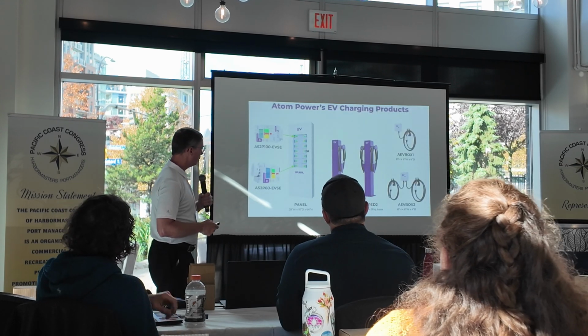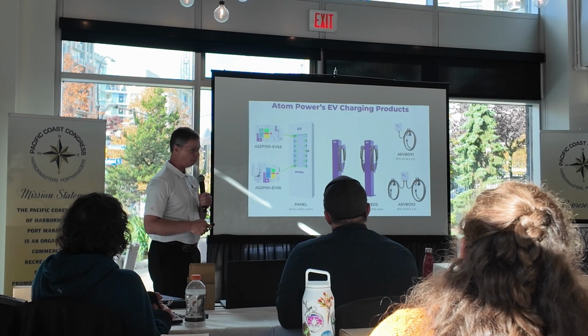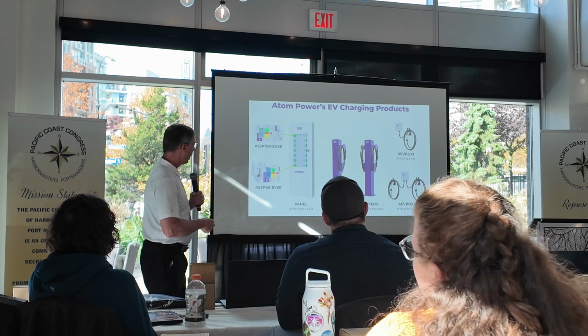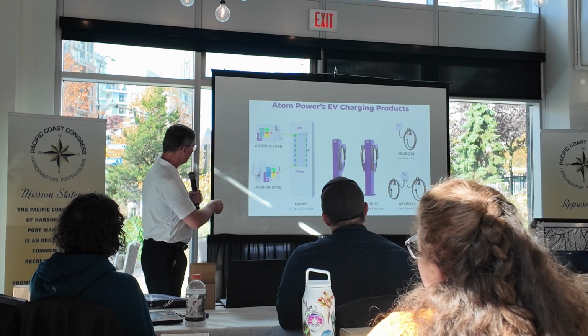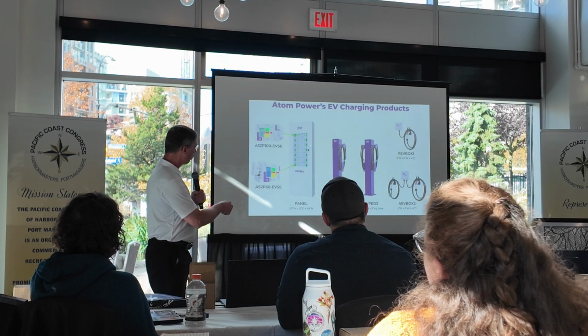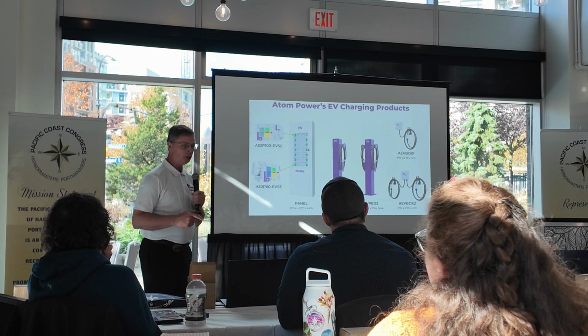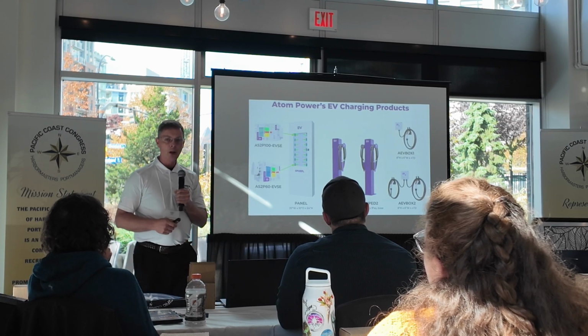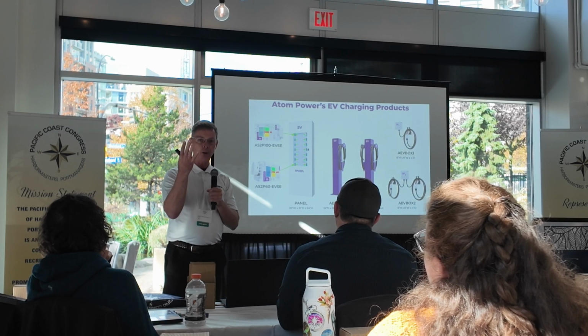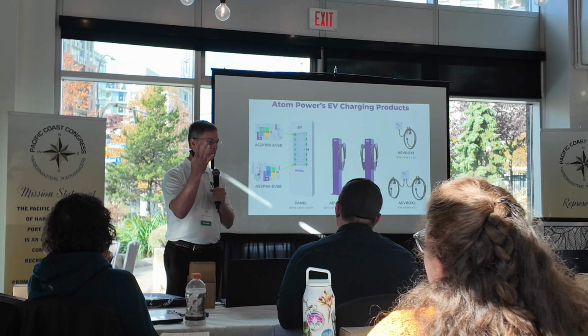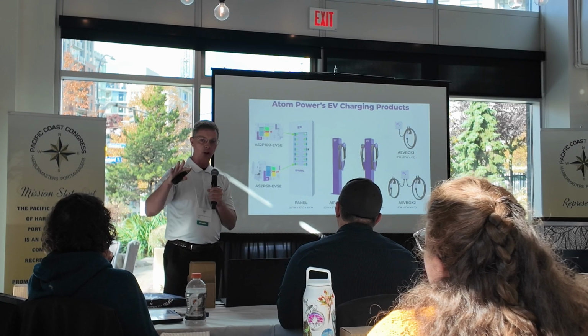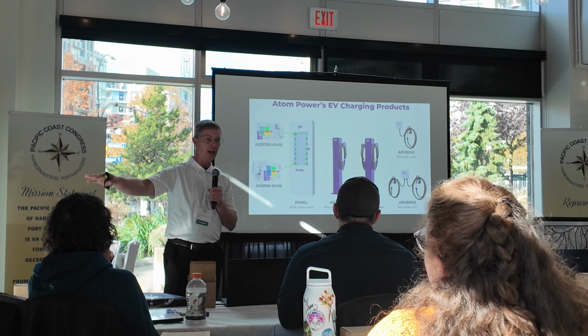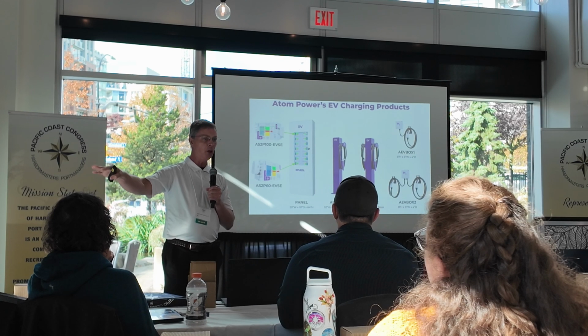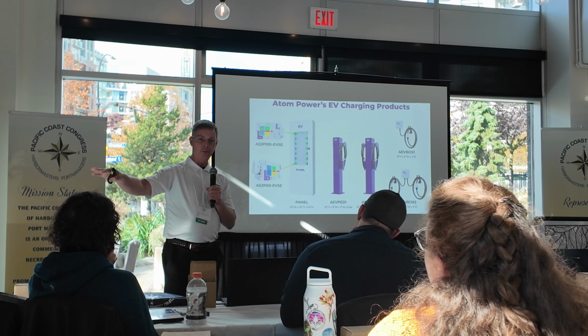And so here's a picture of one that I've designed several times, where you can have each one of these breakers. You can see that's a 100 amp breaker, and you fit 12 of them in here and have a connected load of 1200 amps, but only have 400 amps on the input. So your infrastructure can only be there for 400 amps, but you can control 1200 amps on the output. So you could have 12 boats.